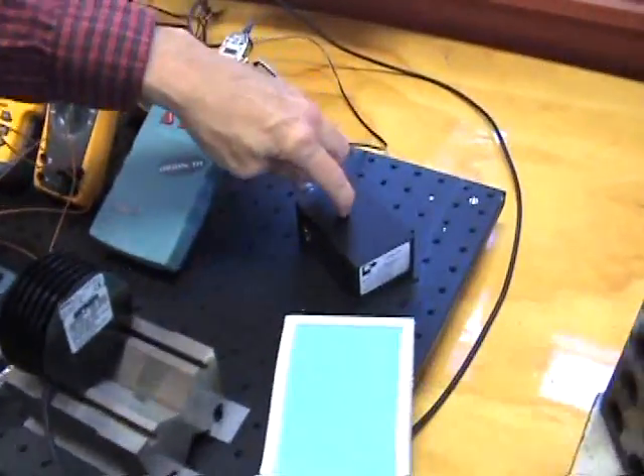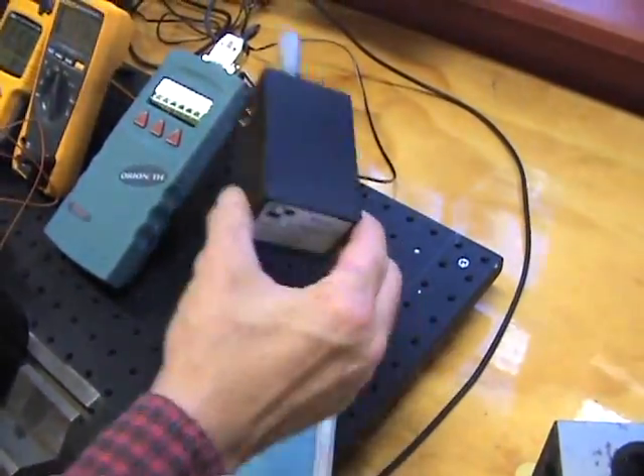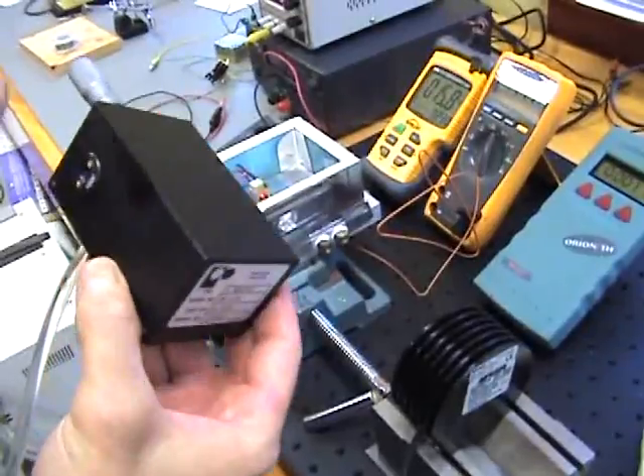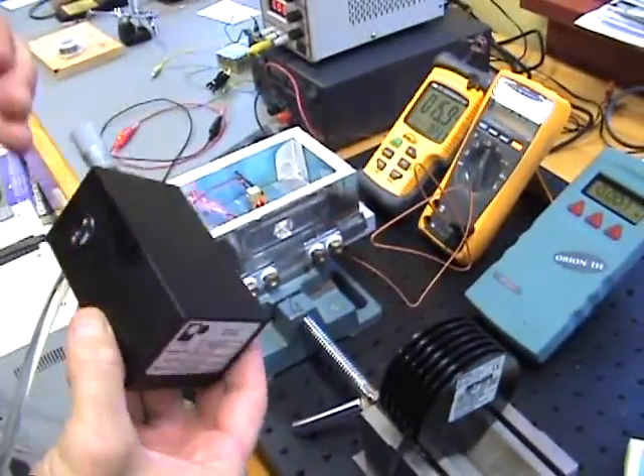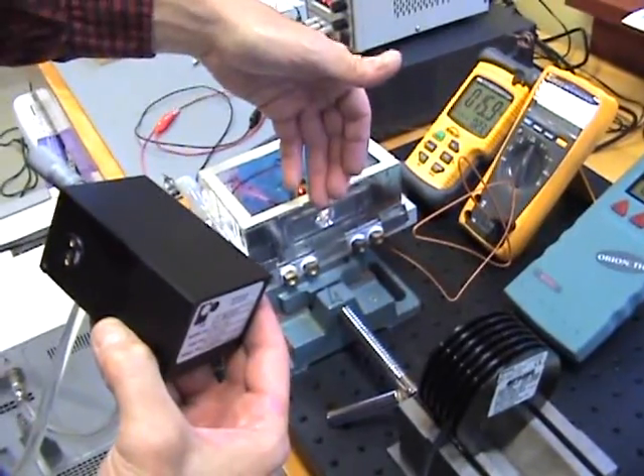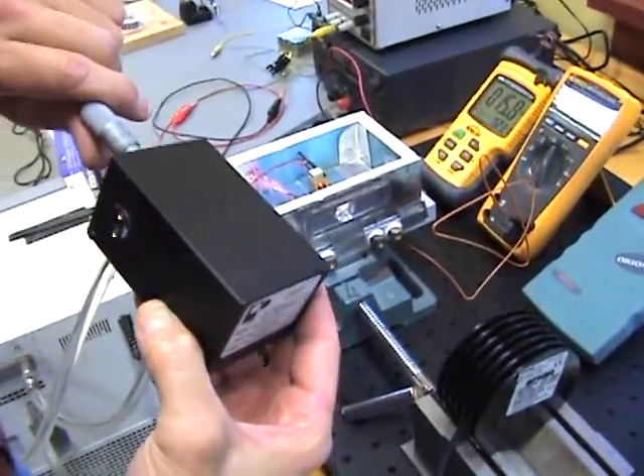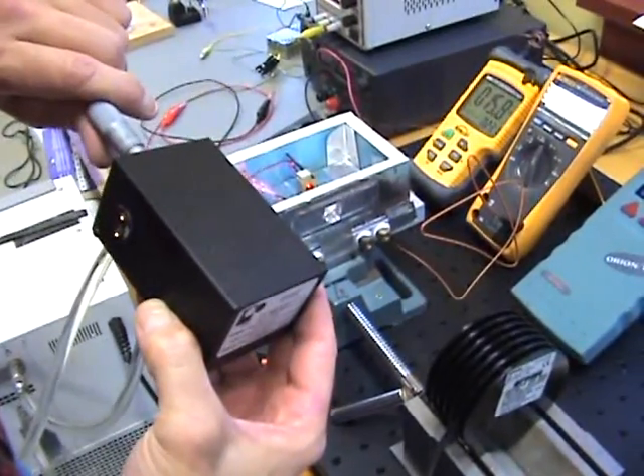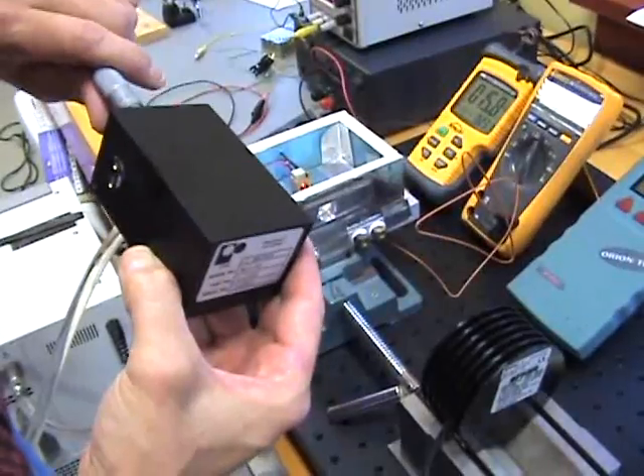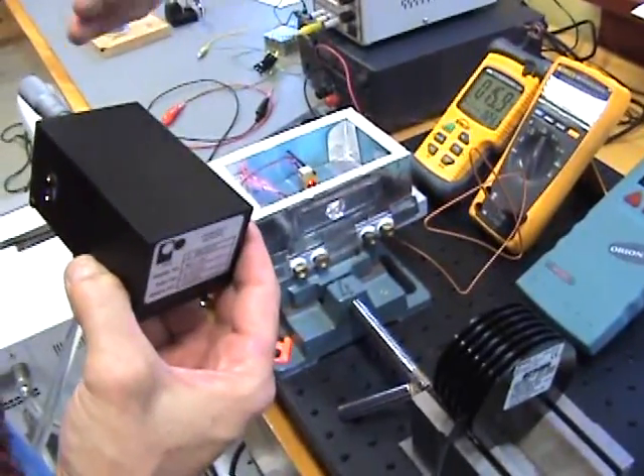And finally, I have a small portable monochrometer here. The way this is set up is, rather than setting up a complicated spectrometer, you just do this visually. You look through one slit at a bright spot, such as the reflected light off the microscope slide. You dial the micrometer here, and the micrometer is set up such that one division equals one nanometer. I've calibrated this against a helium neon laser, which is fairly close in terms of the emission wavelength of the diode, so it's pretty accurate.